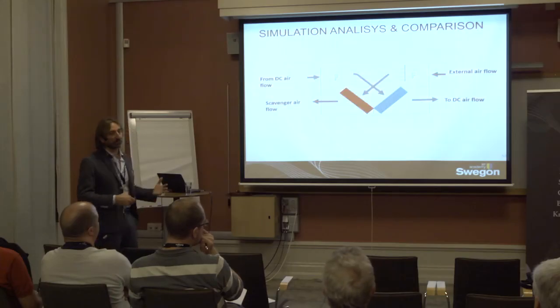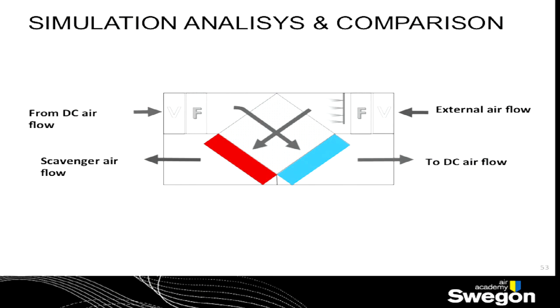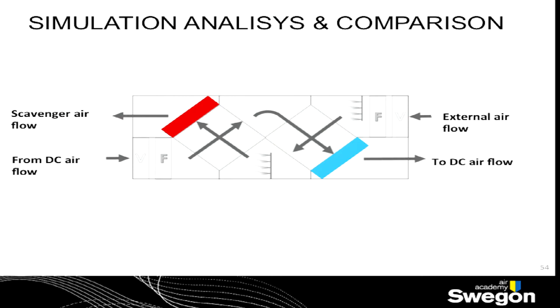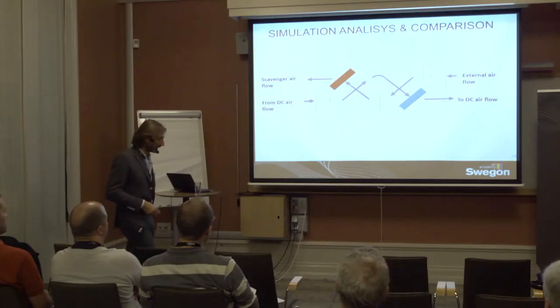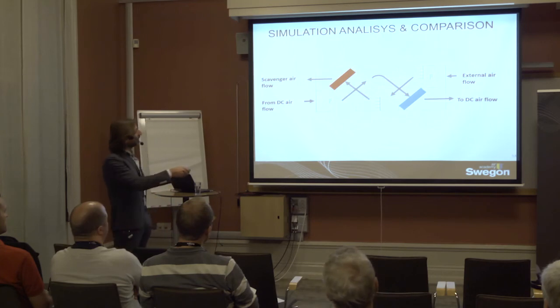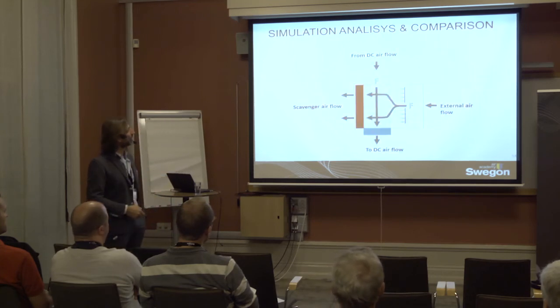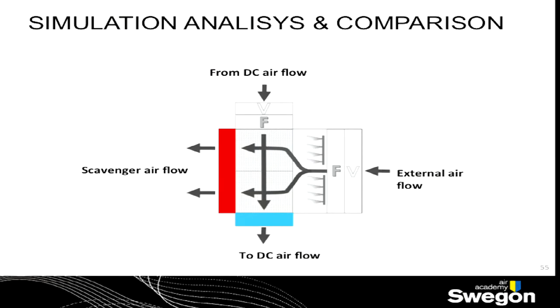And we considered different types of heat recovery heat exchanger, let's say. So based on a single plate heat exchanger system for air-to-air exchange, a series-to-series plate heat exchanger, so both the air from the data center is crossing both of the exchangers, and the external air is doing just the same. Or a system like this one with a series-to-parallel flow, because the external flow is not crossing both in series, but only the air from the data center. We made this kind of analysis just to have a complete overview of what is happening with this kind of system.